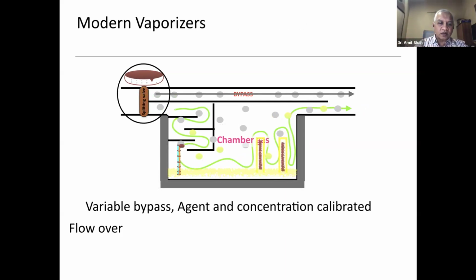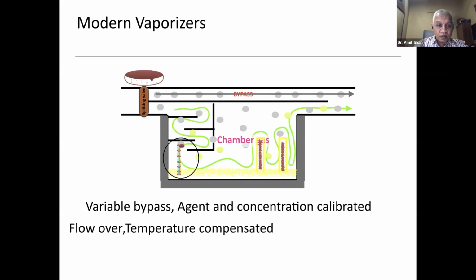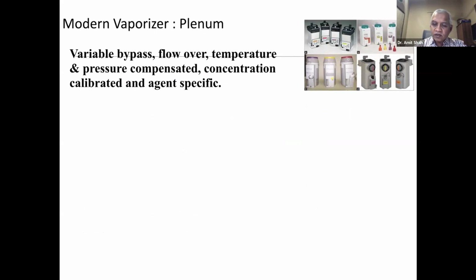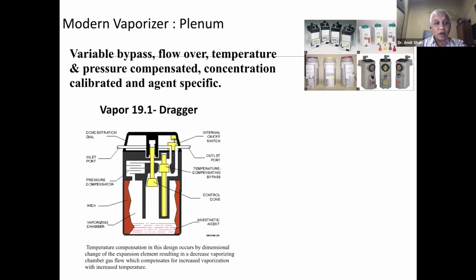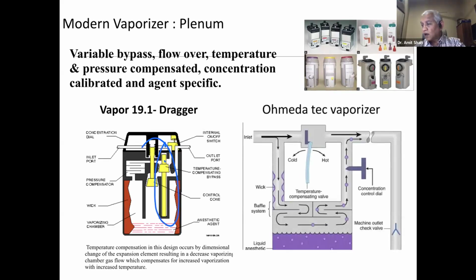So now our modern vaporizers are variable bypass, agent specific and concentration calibrated. That means there is a splitting ratio which is fixed with that splitting valve. It is flow over, it is temperature compensated, and it is back pressure compensated. So this is the characteristic of our modern vaporizer. So there are various types of vaporizers: variable bypass, flow over, temperature and pressure compensated, concentration calibrated, and agent specific. Vapor one is from the Draeger company, which, as I said, is using this metallic rod for the compensation, while Tec vaporizers are using this strip, two metal strips which can bend. So these are the Draeger and Tec vaporizers.